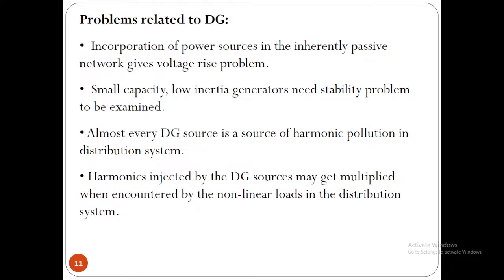As you know, in a converter circuit we use devices which can be turned on and turned off constantly, and as a result harmonics are generated in the inverter itself. It is a natural phenomenon. Whenever you use an inverter from DC to AC, harmonics will be injected. The reason is that it is not a pure AC; there is always a source of harmonics. So whenever you inject power, you are injecting harmonics into the system itself. This cannot be allowed. You are polluting the whole system.